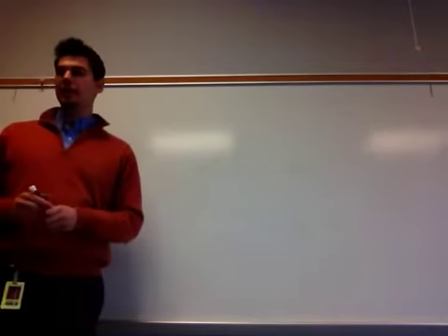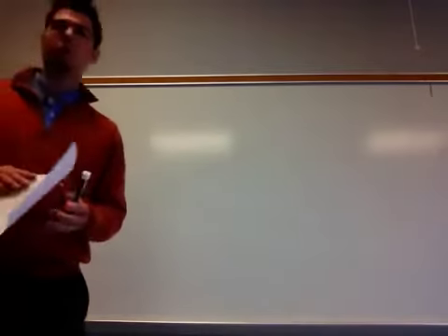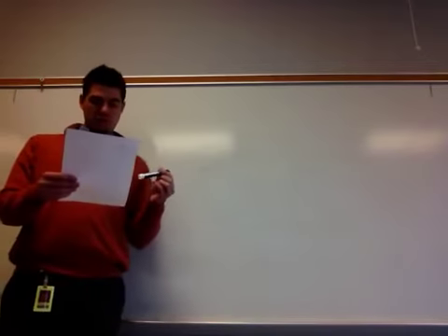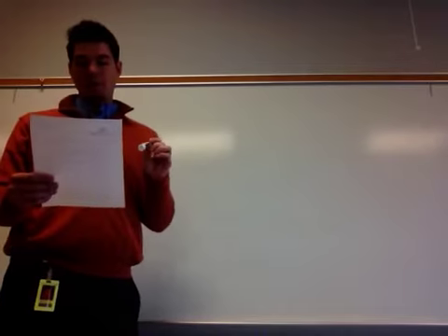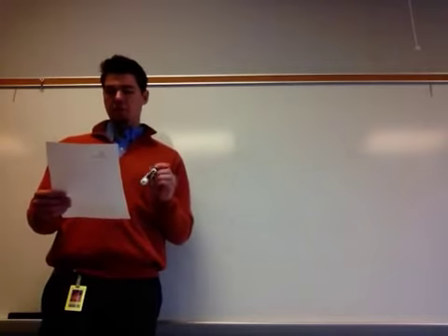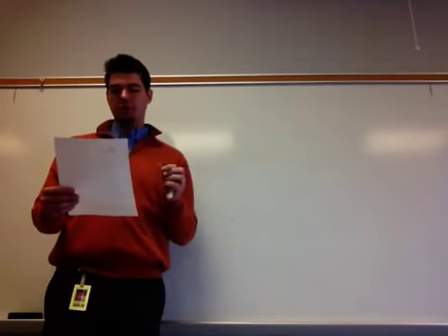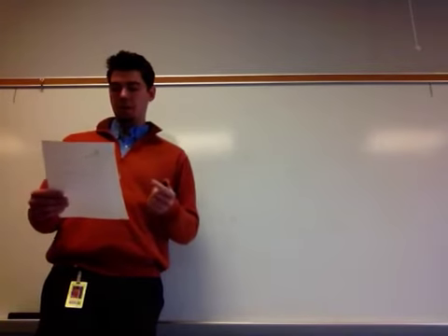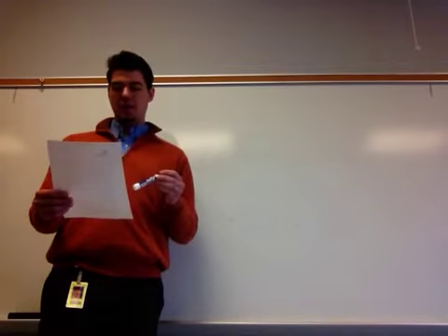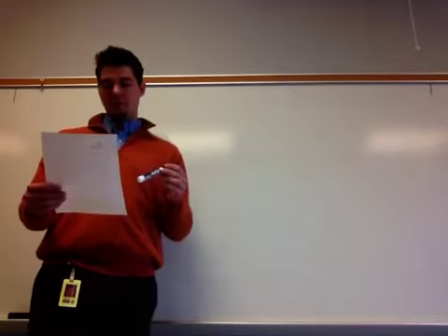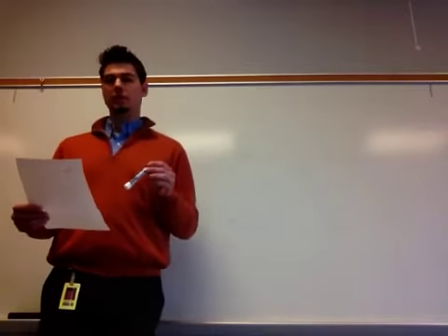All right. So with that being said, I'm going to do question number 7 on the homework, which is: how many 225 watt modules, each having a VOC of 42.6 volts and a temperature coefficient of negative 0.67%, so we're using percentage coefficient calculations, are needed in a series string to maintain the 620 volt minimum of the grid tie inverter when the record high temperature is 35 degrees.